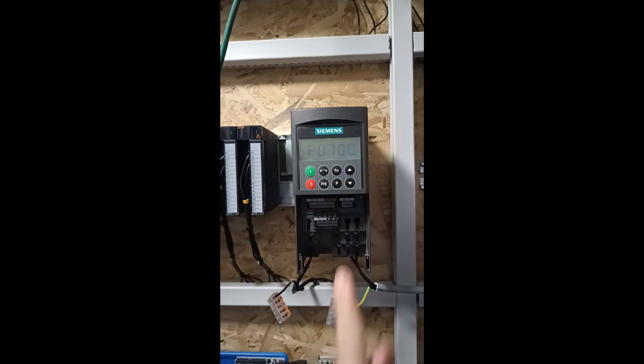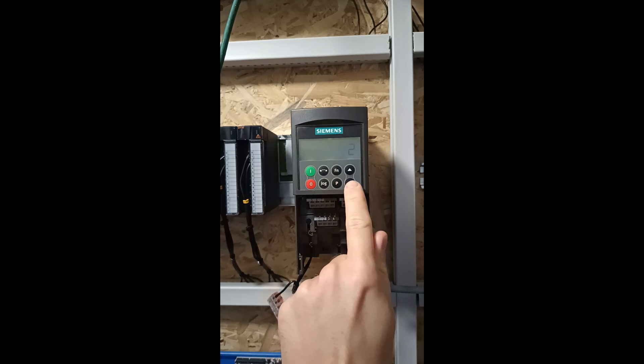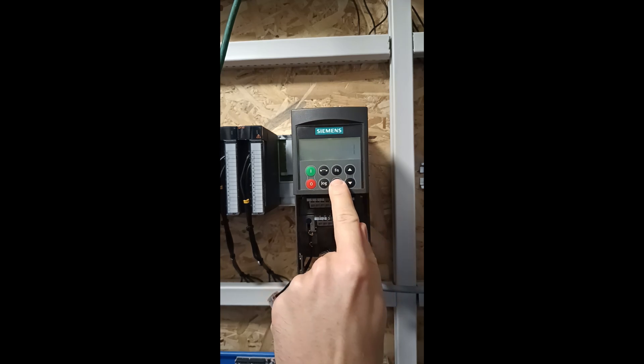Parameter 0700 we want to set to 1. This lets the drive know we want to control it locally from the panel.